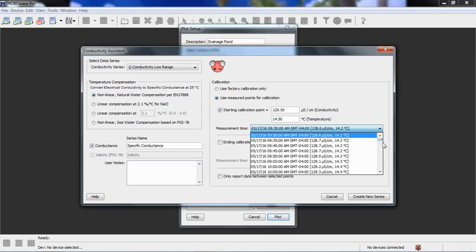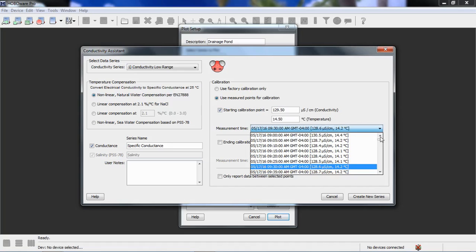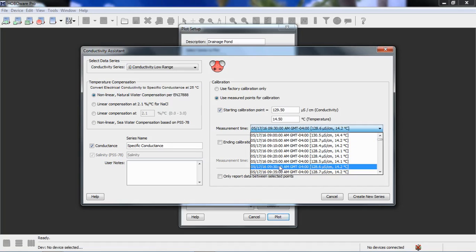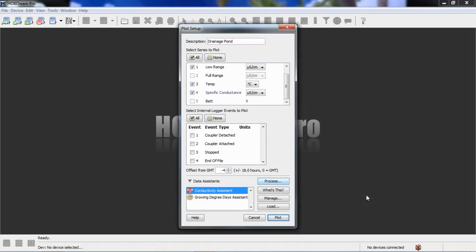We are going to use a starting calibration point. It's a very short deployment, so we don't have to worry about fouling. So I'm going to deselect the ending calibration point. And I'm going to put in my measured values that I measured when I was out there, 129.5. And the temperature I recorded at the time was 14.5 degrees C. And we're going to correlate that to a point in the data file. We want to make sure that the logger was stabilized to temperature. We took that measurement at approximately 930, so we're going to correlate that with that measurement right there. And we're going to click on create new series.